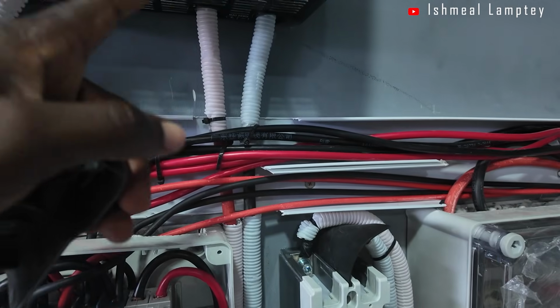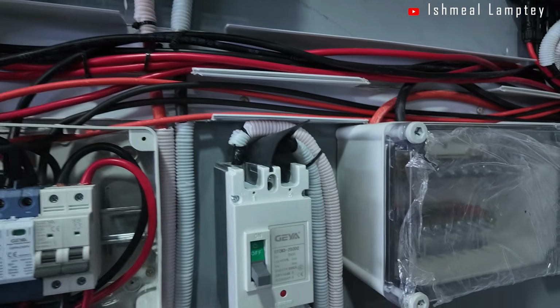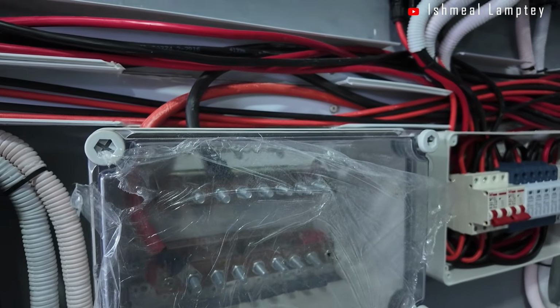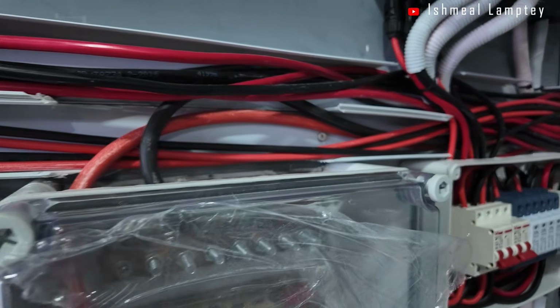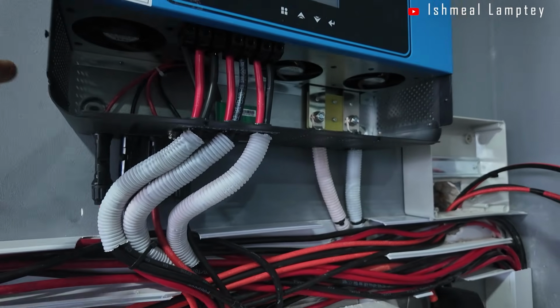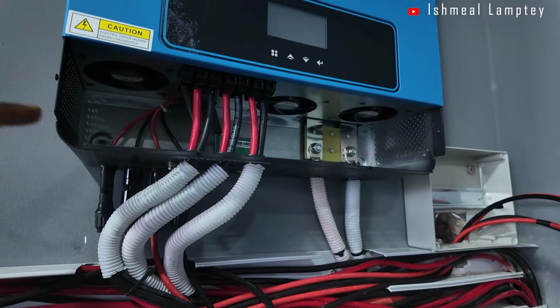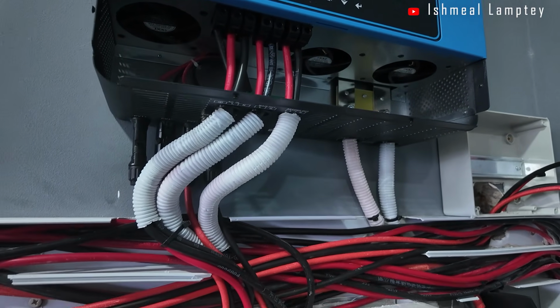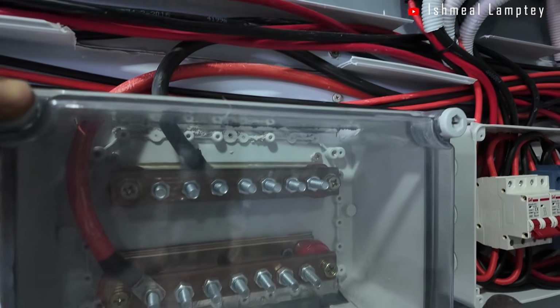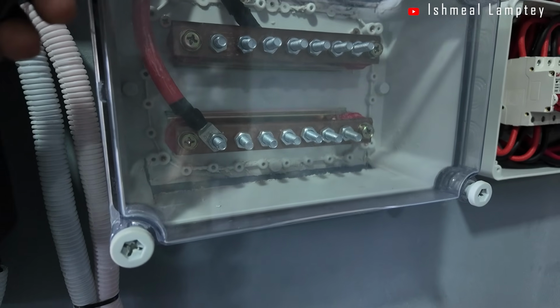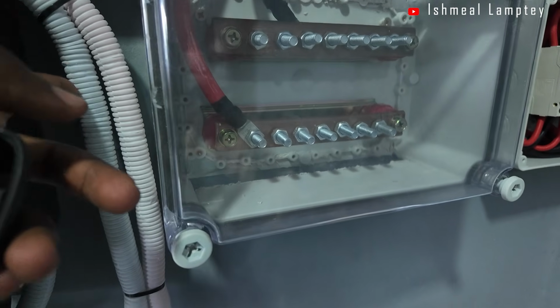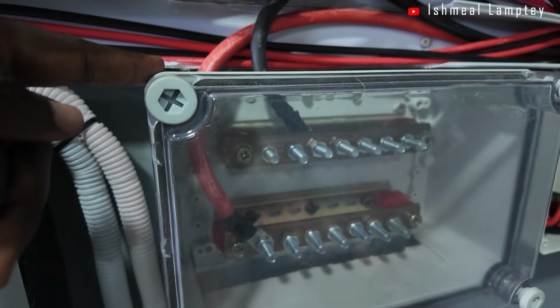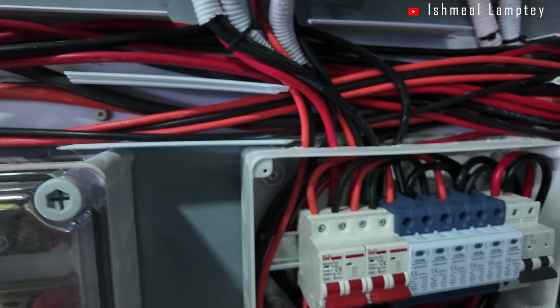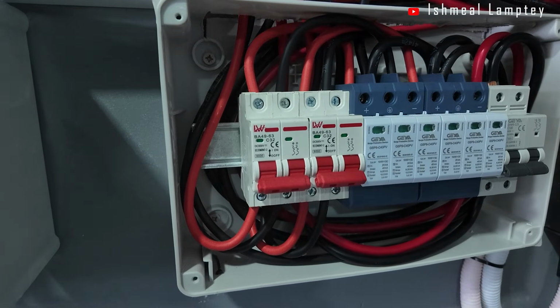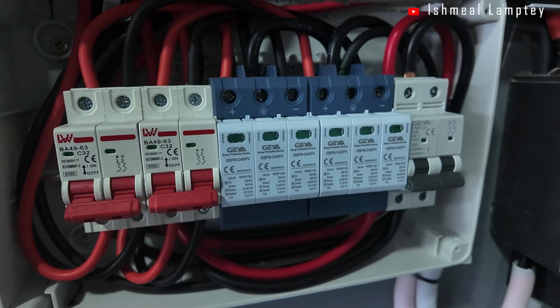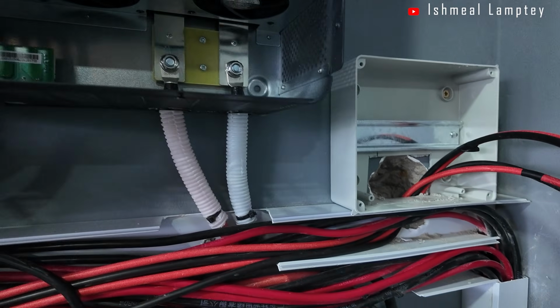So for the breaker box, we had 2 SPDs, 1 AC breaker, and 2 DC breakers, making a total of 5 components in one breaker box, and the same for the other breaker box. All those cables were routed in the trunking, and then we did the configuration to the inverters, each inverter having its own set of cables. We also had the panels' line coming in to a junction box.